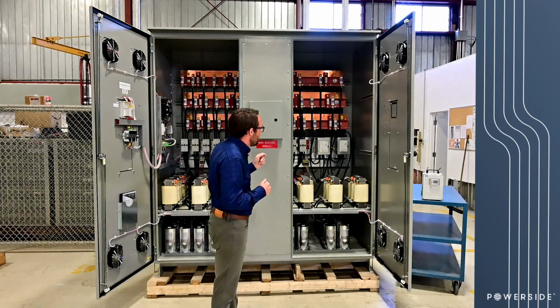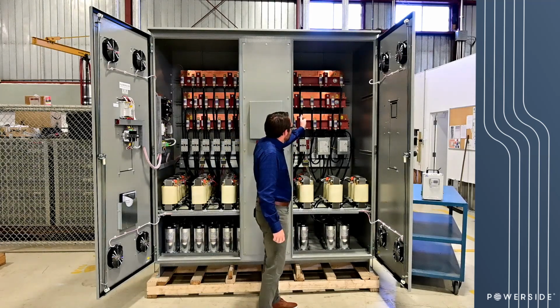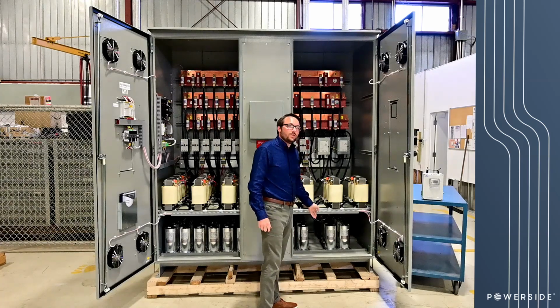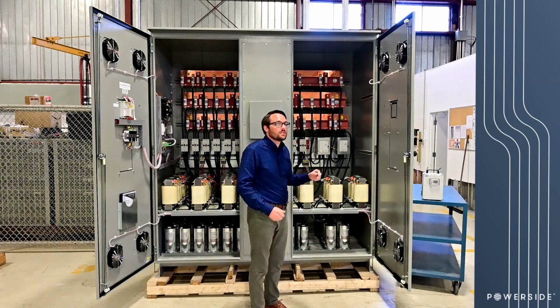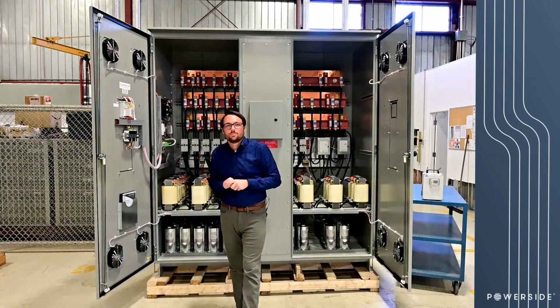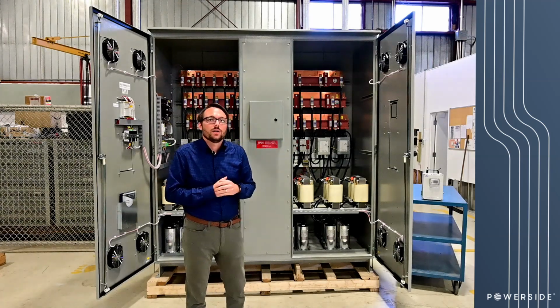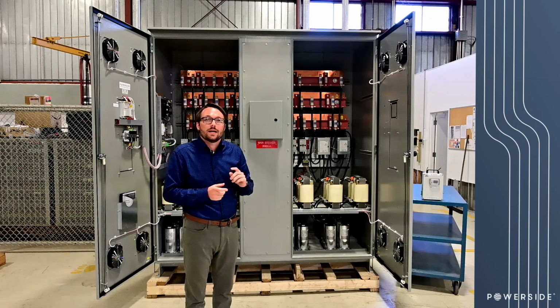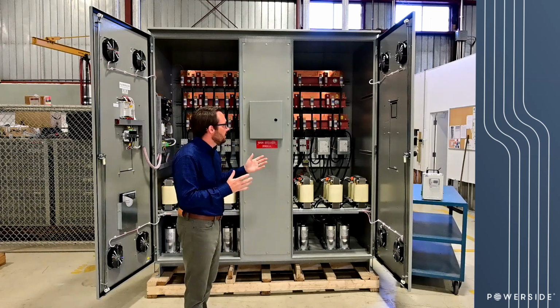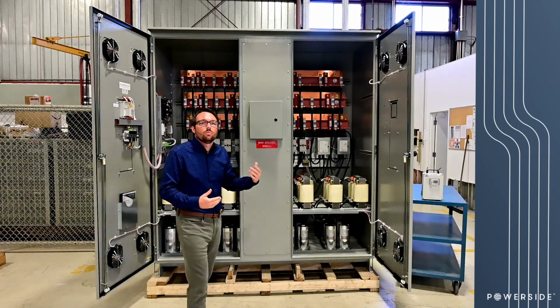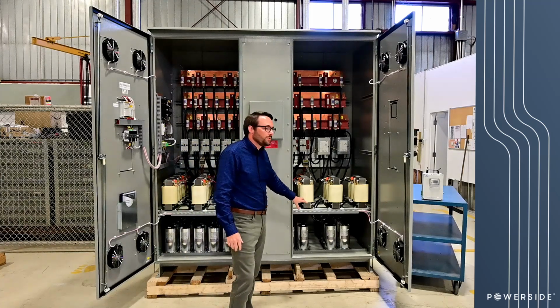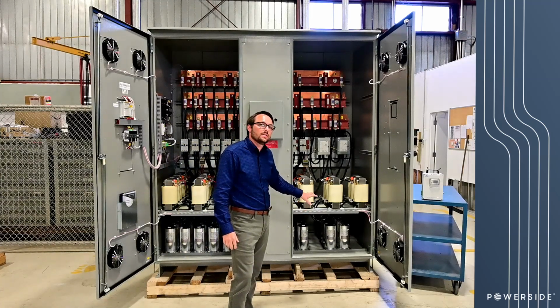And the way that it does that is there's a direct connection for B phase all the way through, and then A and C phases are switched at the zero voltage crossing point. It's basically a transient free switch, so we can turn them on and off as quickly as needed, as the load changes, without having to worry about discharging voltage in the capacitor cells.